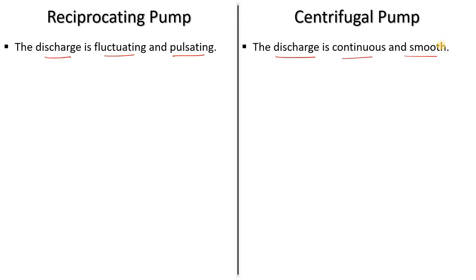Why is reciprocating pump discharge fluctuating? In the reciprocating pump, first you expand the boundary — liquid comes in — and the discharge does not go out. Then when you compress, the suction valve closes and discharge valve opens. So the discharge is not continuous — it fluctuates, and pulsation is created on the discharge side.